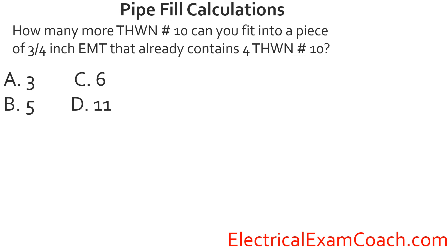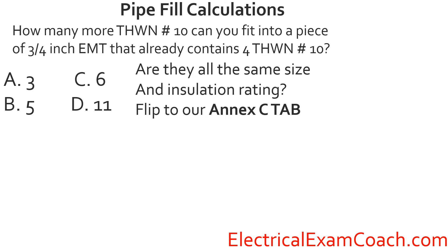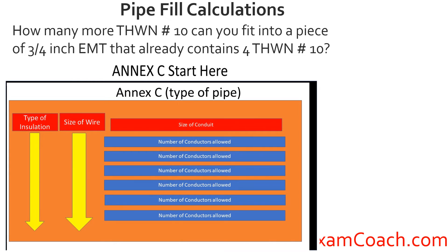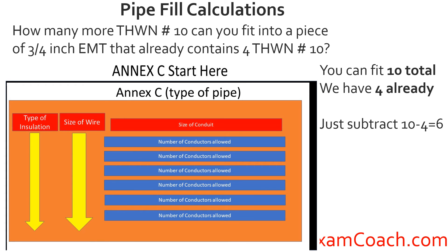Practice problem: How many more THWN number 10 conductors can you fit into a piece of 3/4-inch EMT that already contains four THWN number 10s? Are they all the same type and insulation? Yes. Head to Annex C, find EMT — not the A version — cross to the page number, read the black bold heading, find THWN insulation and size 10 wire, come across the top to 3/4-inch conduit and tee off. The table shows we can originally fit 10. Since four are already in the pipe, 10 minus 4 equals 6 — we can fit six more.